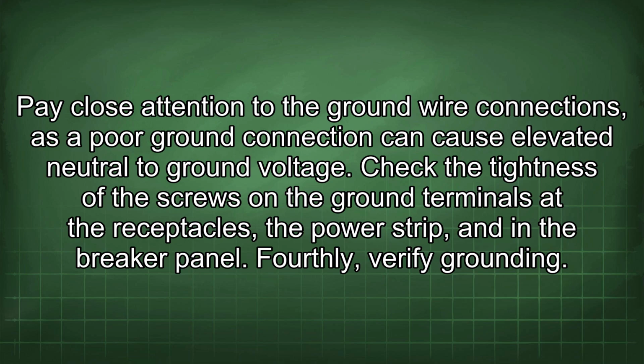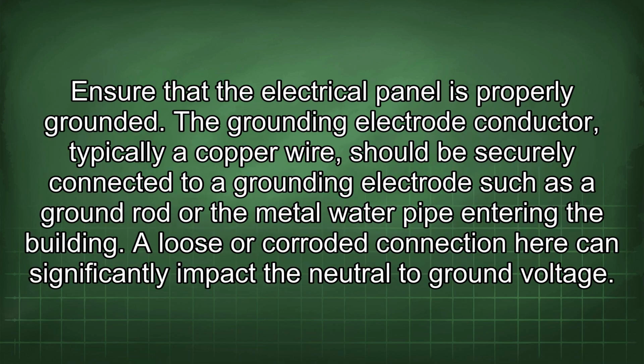Check the tightness of the screws on the ground terminals at the receptacles, the power strip, and in the breaker panel. Fourthly, verify grounding. Ensure that the electrical panel is properly grounded. The grounding electrode conductor, typically a copper wire, should be securely connected to a grounding electrode such as a ground rod or the metal water pipe entering the building. A loose or corroded connection here can significantly impact the neutral to ground voltage.